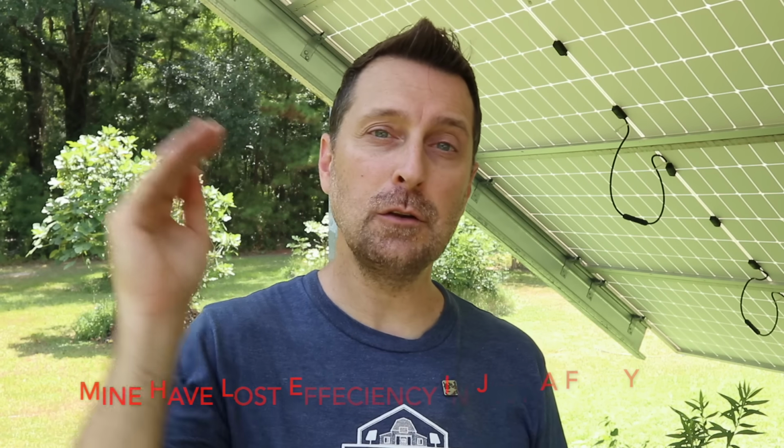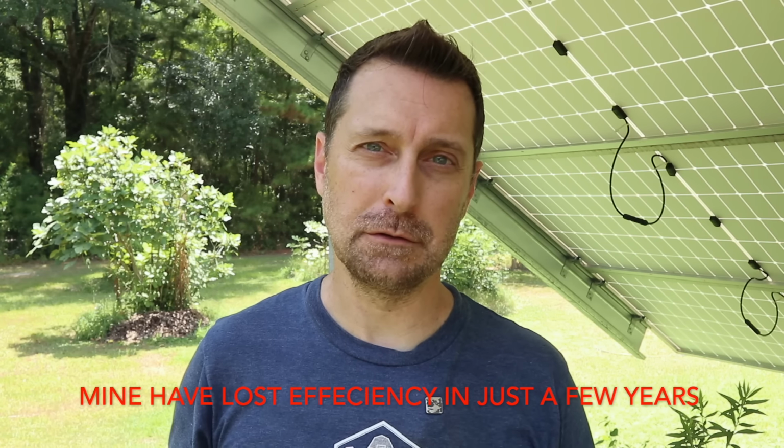And that can happen in the summertime when your panel production drops. And the voltage drops, which means you are under the threshold for that MPPT. Then it will click off and not draw any amps through it. And if you start off with a string that is at that lower threshold, and over time, some of your panels lose efficiency, then you could go under that voltage. And then that MPPT won't start back up.